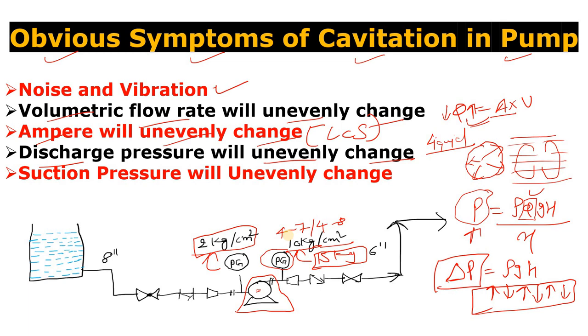If you have a doubt about cavitation and need to check it in the field, you must check all five symptoms: first, noise and vibration; second, volumetric flow rate; third, ampere; and fourth and fifth, discharge and suction pressure. Please let me know in the comments what prevention steps you would take if cavitation is occurring in a centrifugal pump. That's all for today's video — thanks for watching, keep learning.